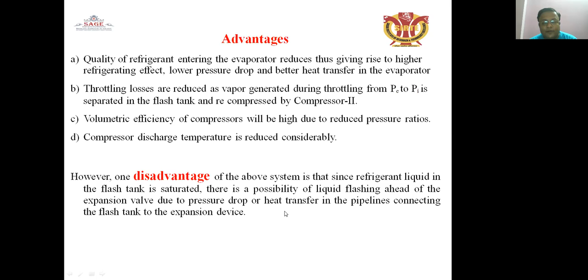However, one disadvantage of the system is that since the refrigerant liquid in the flash tank is saturated, there is a possibility of liquid flashing ahead of the expansion valve due to the pressure drop or heat transfer in the pipelines connecting the flash tank to the expansion device. There are chances of this if the expansion is done down to a low pressure. There will be a pressure drop or heat transfer in the pipeline connecting to the flash tank. That will decrease the refrigerant effect.